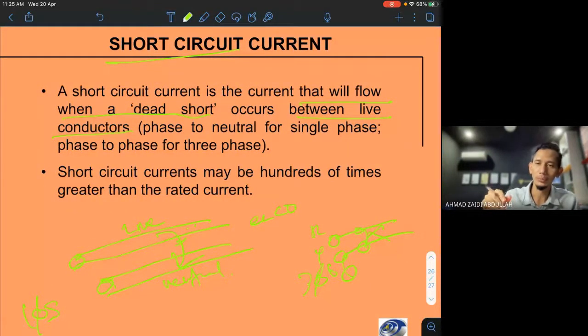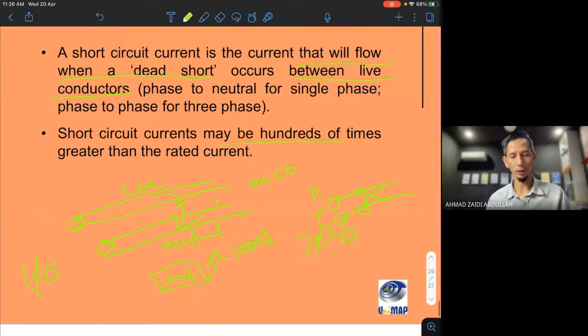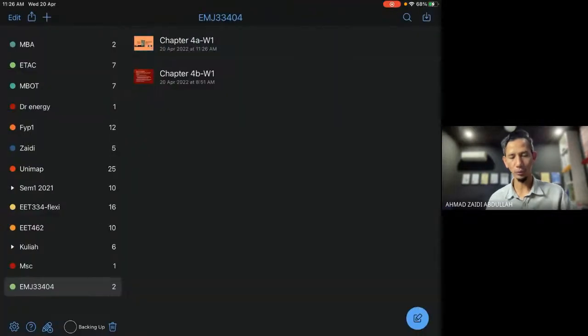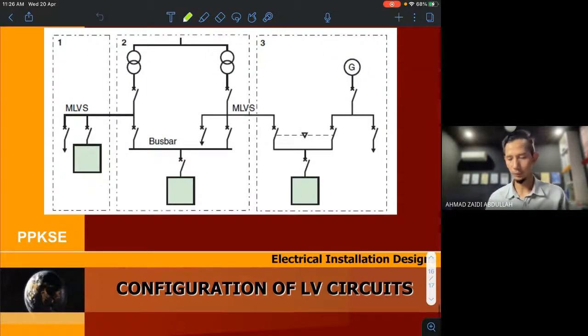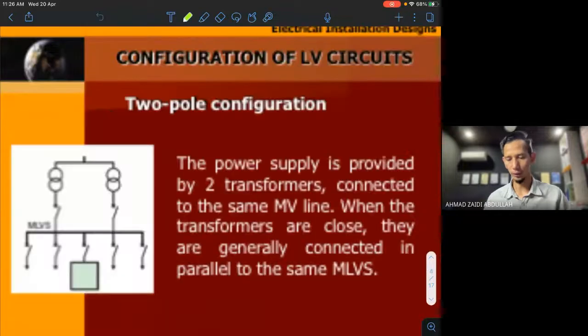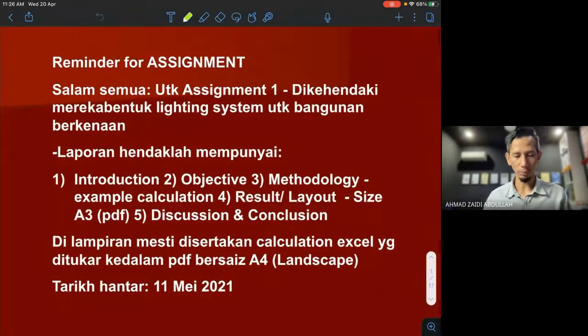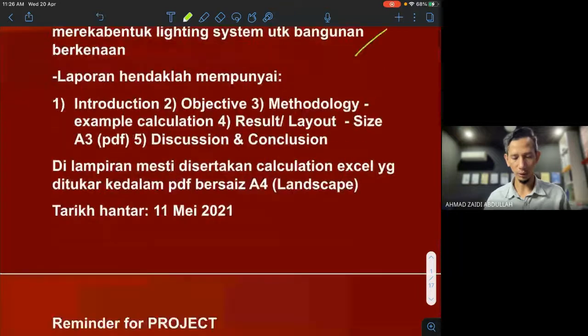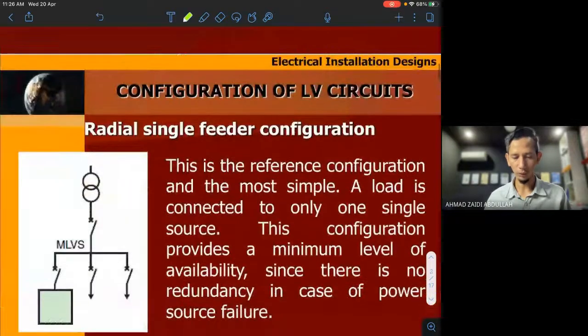But if not tripped, something else will happen because it may be 100 times greater than the rated current. So let's say we set the current at 20 amp. When the short circuit happens, it can be 2000 amp. So very, very dangerous. Okay, so that's all for the first slide. And then we go to the second slide. Very short briefing. So reminder for the assignment, I think I already reminded all of you.